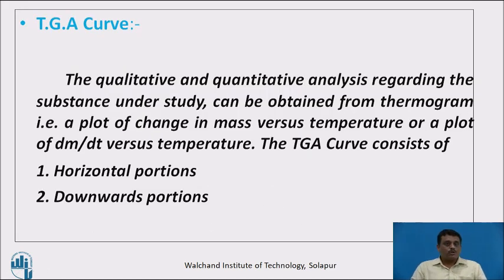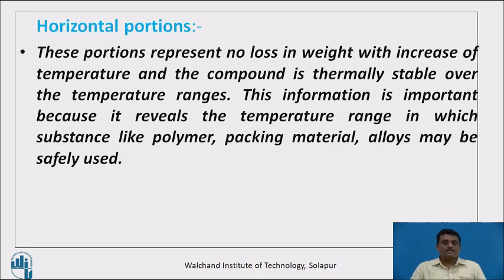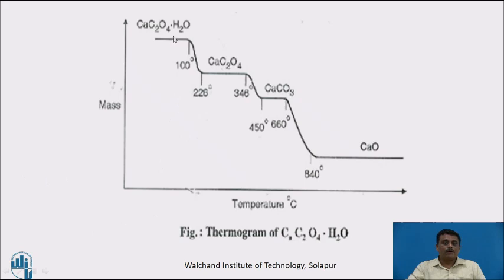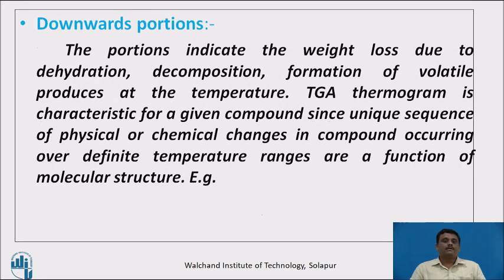The TGA curve consists of two types of portions. Qualitative and quantitative analysis can be obtained from the thermogram — a plot of change in mass versus temperature, or dm/dt versus temperature. The TGA curve consists of horizontal portions and downward portions. Horizontal portions represent no loss in weight with an increase in temperature, meaning the compound is thermally stable over that temperature range. This reveals the temperature range in which substances like polymers, packing materials, and alloys may be safely used.